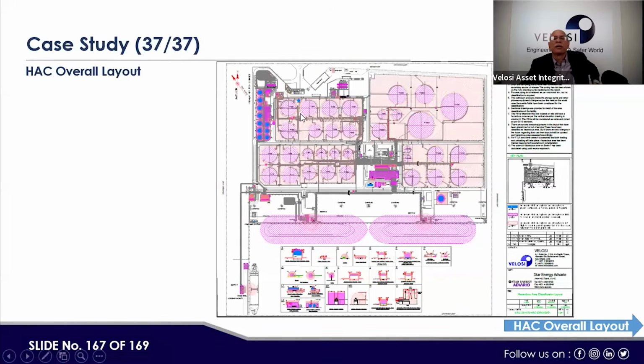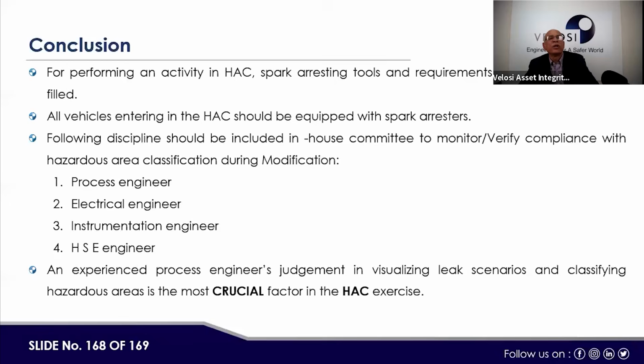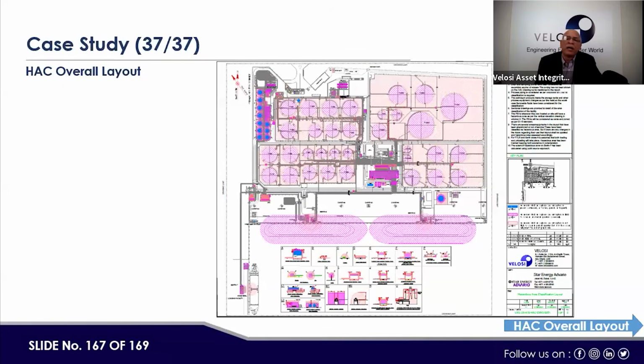And here the applicable zones are shown, zone 1 and zone 2. Zone 0 is not shown because zone 0 is shown only if there is a drawing with an elevation view. So in conclusion, we have prepared the schedule and the hazardous area classification. The next thing is the preparation of the electrical and instrumentation equipment list and their applicable class as per HAC. That is the secondary job, which is not being presented here.